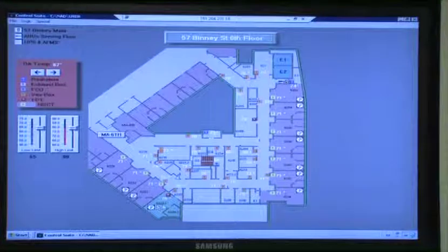We did clarify what's going on here, so we have to make those modifications and changes. This is completely... It's not an isolation room. It's called a protective environment room. It's positive, it's not negative. We have to take it away from any kind of isolation wording, because it's really not isolation, it's protective, what's called a protective environment room. It is no different than any of these other rooms up there, other than it has an ante room. It's fully functioning the exact same way as any one of these rooms.